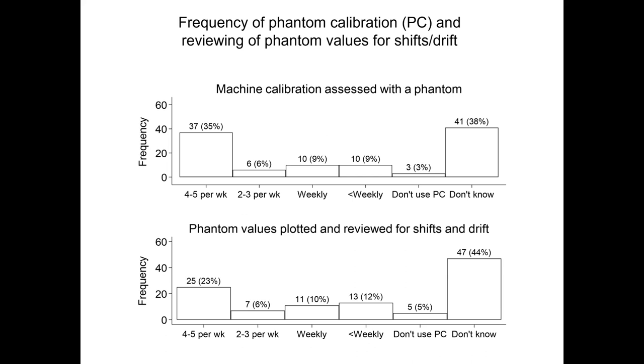In only 37 of the centers, 35% overall, was machine calibration using a phantom undertaken on most days of the week. In a further 6% it occurred 2 to 3 times a week, and a further 9% weekly. So in about 50% of the participating centers, we had either no knowledge of calibration or it was undertaken at less than weekly intervals.